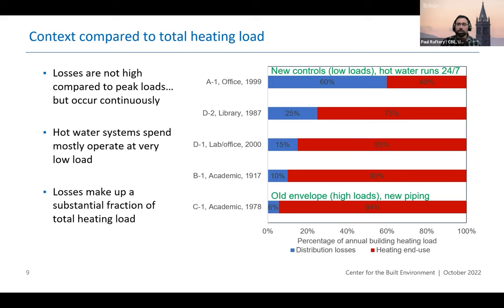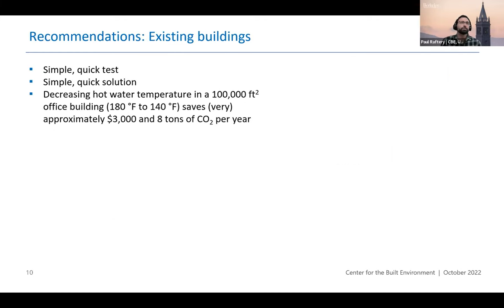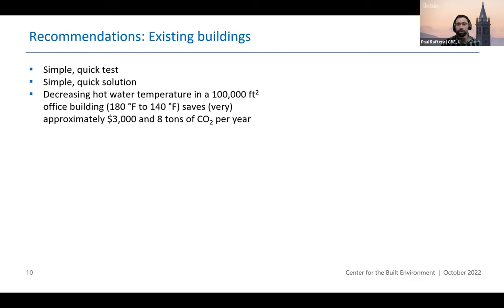So it's something to consider in any building you're working on, whether you're an operator or a designer. For existing buildings, this is a really simple and quick test to do — you can effectively get results overnight or over a weekend. And the solution, at least a partial solution, is also quite quick: just implement lower hot water supply temperatures or an actually functioning hot water supply temperature reset.